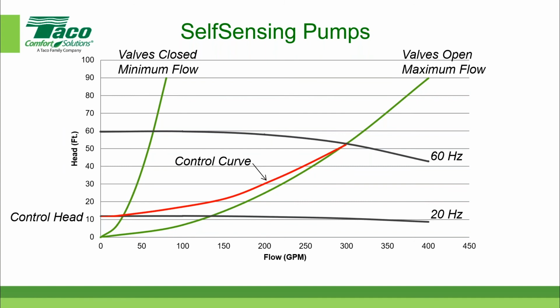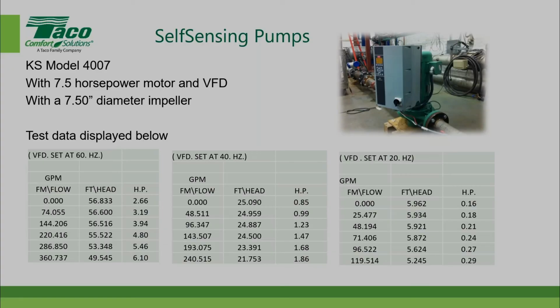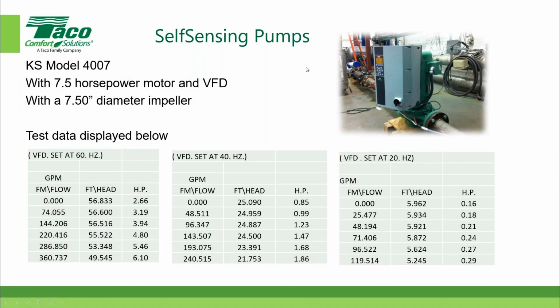Actually, we have a question. If you can go back to your slide that shows the different speeds in the table. Yep, yeah. Go ahead. So, do you not end up with crossing curves? For example, at 60 hertz, at 3.19 horsepower, you get 56.6 feet. There might be a point at 50 hertz where you have 3.19 horsepower that would correspond to a different head and GPM. That's true, but not at the same speed.